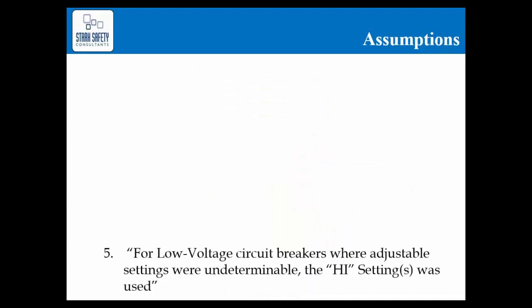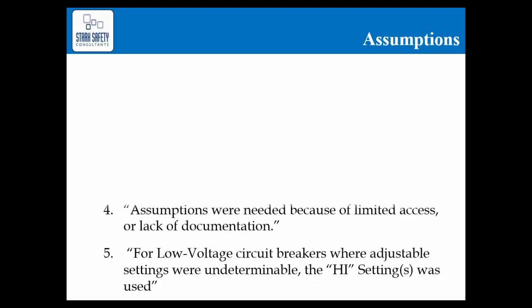The first one is number 5: for low voltage circuit breakers where the adjustable settings were undeterminable, the high setting was used. That takes a lot for granted, not to mention making it impossible to do coordination accurately.